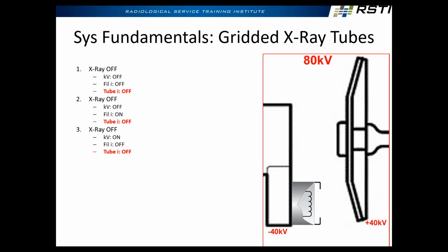But manufacturers will do this. They will leave the KV on and only control the filament, because it's a lot more power to turn the inverter on and off. They'll leave it on, and they can turn the filaments on and off for what's called pulse fluoro. Yeah, you wouldn't see any, so none of these so far have made any radiation, no x-rays. Now I've applied KV, I've applied filament current, and now I have tube current, which is MA, and therefore radiation.